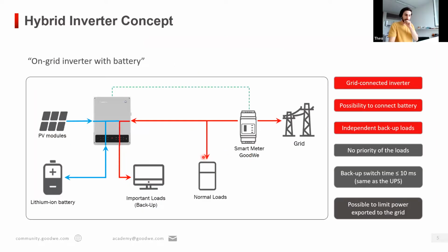However, if you want to have storage inverters, then we offer basically 2 different types of inverter technologies. First, we have the hybrid inverter, and to explain the concept of our hybrid inverter, we have this picture here. This is basically an on-grid inverter with battery. Here you see the inverter and the different connections. Exactly like a normal PV inverter, you have the PV modules connected here with DC, and then you have some AC power going out here where you connect the loads, or you have the excess energy exported to the grid.